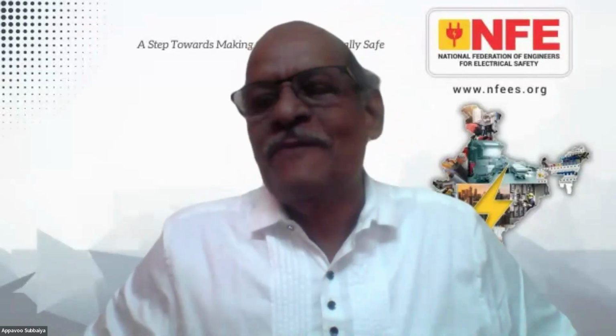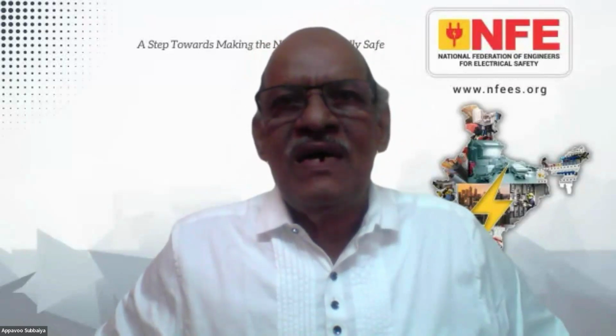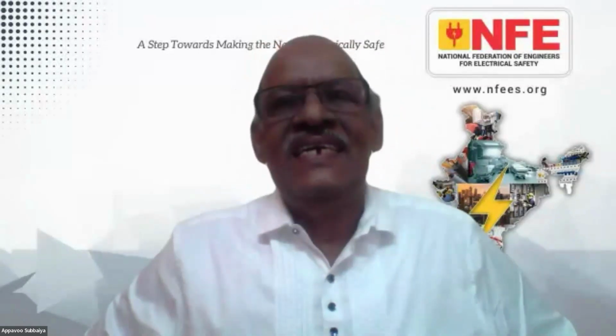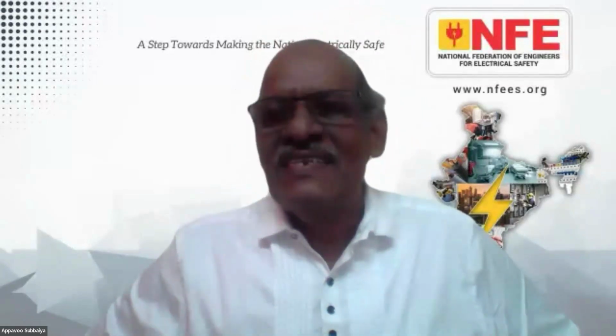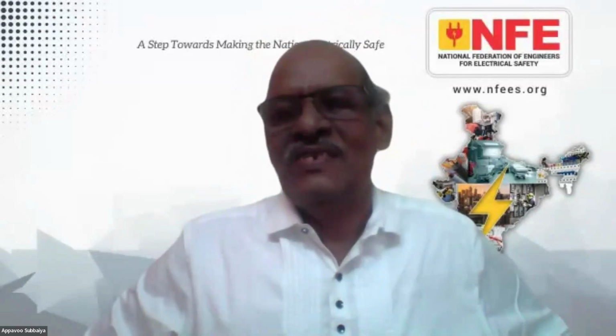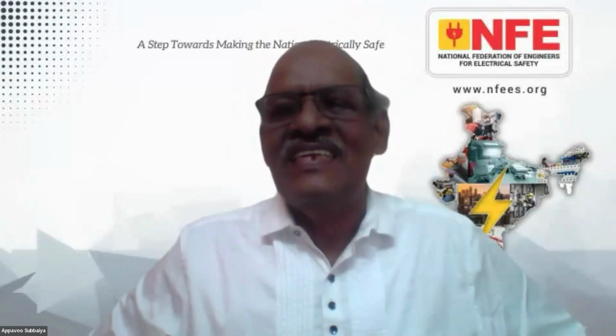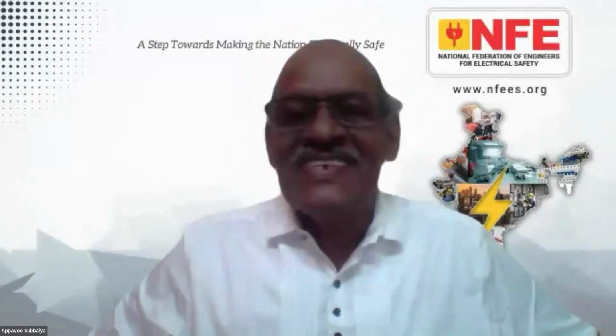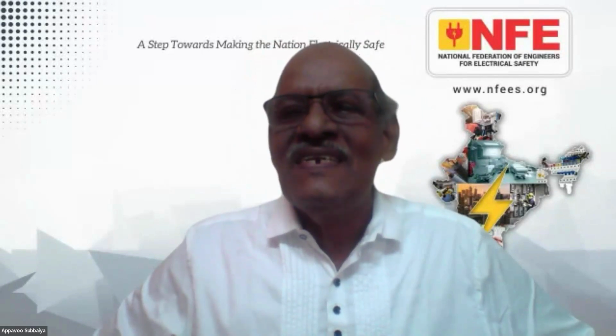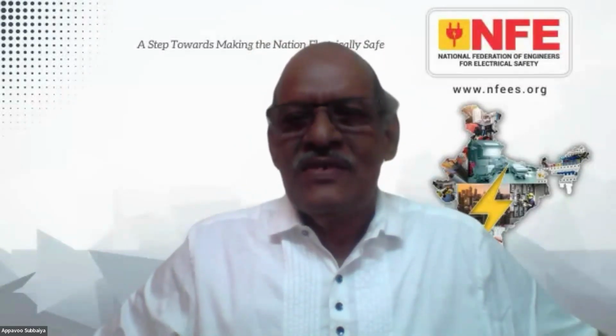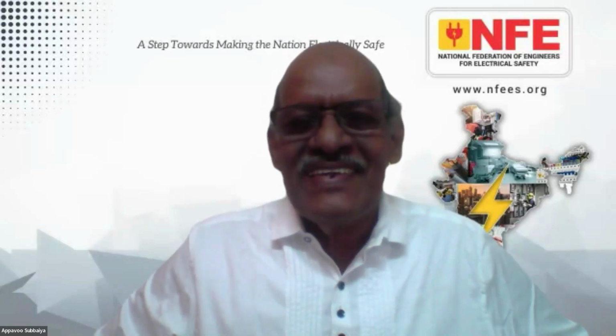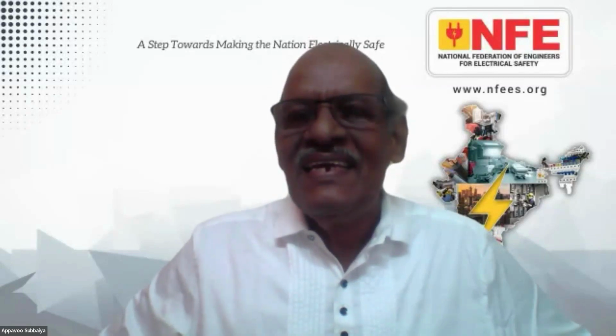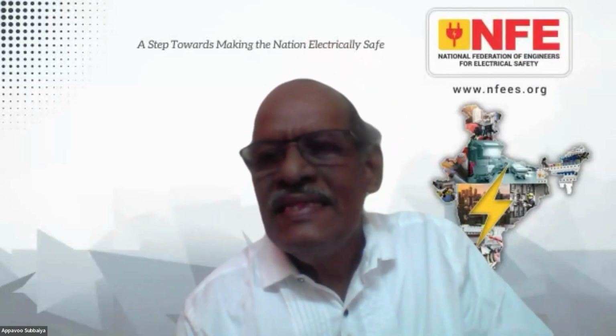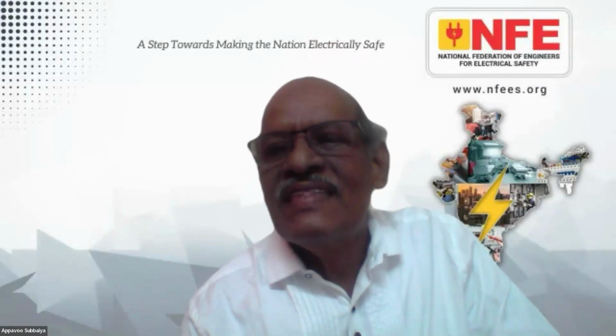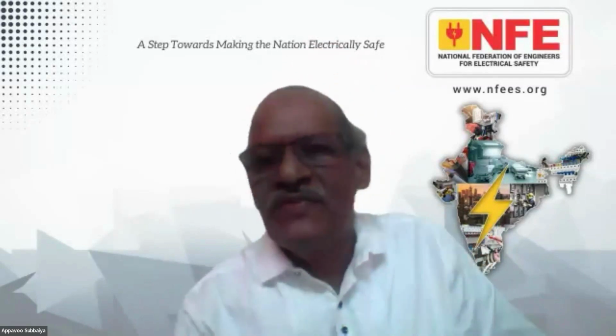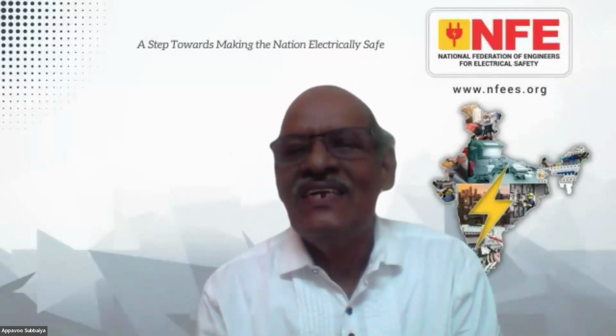Thank you for a vital point. The clearances stipulated in the regulations are the minimum. You have to add the sag if it is a vertical clearance. If it is a horizontal clearance, you have to take the wind force into account. If a person comes with a lengthy 10 feet rod, these are all interfering with the supply. This is an illegal activity; there is another provision where the supplier's land should not be infringed. If there is an activity from your balcony in the vicinity of a 66 kV or 110 kV line, it's a violation. You are interfering with the supplier's network. So the clearances given are for the building, and there are clearances for the roads, for the streets, everywhere. It doesn't mean that you can carry anything interfering with the line.